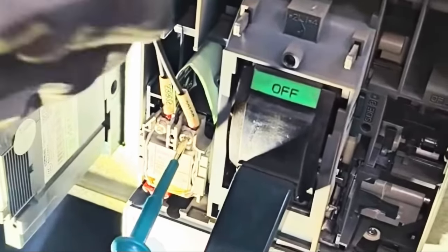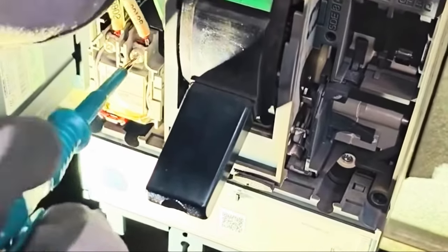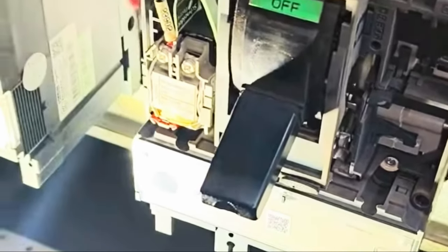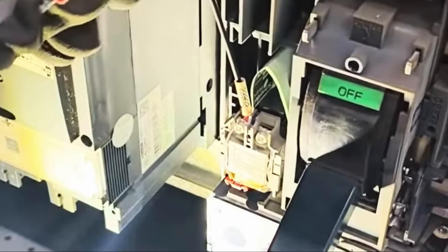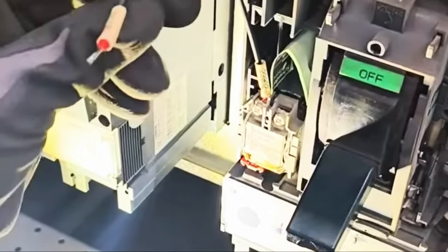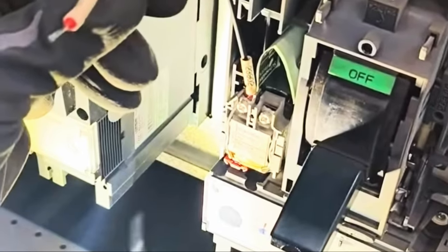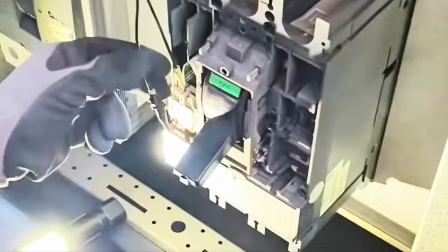So friends, now we are doing a live demonstration with our defective MCB. This MCB is not closing. So now we open the front panel of the MCB and remove the connection of the under voltage relay, because the only safety device in this breaker is the under voltage UVR relay. The UVR works by sensing voltage. It needs to sense whether the exact voltage is present or not. When the exact voltage is not present at the UVR, the breaker should not close.